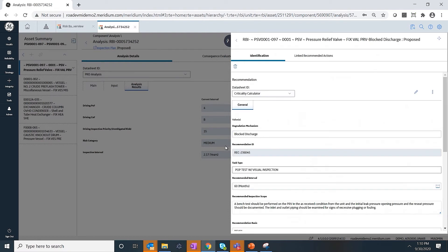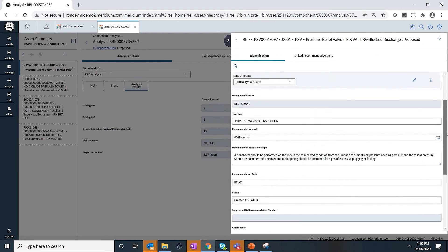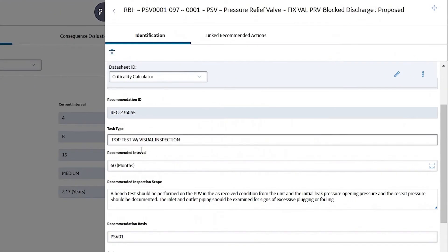So it helps you to tell you what is the risk based on your current time-based program, but it also recommends what should be the best optimized intervals. Based on an RBI program, it tells you that you can extend your interval to 60 months, and it also gives you a recommended inspection scope of work.